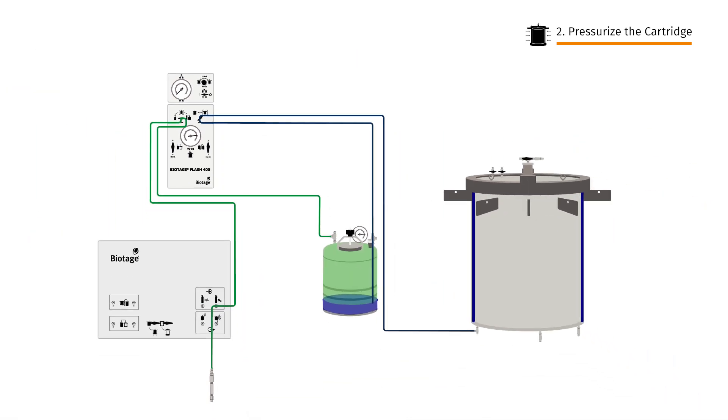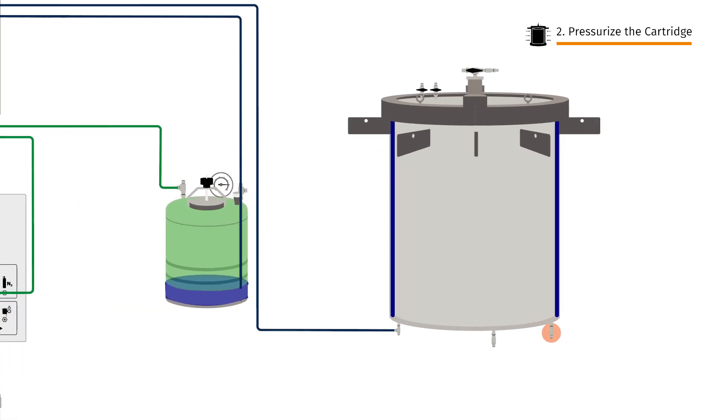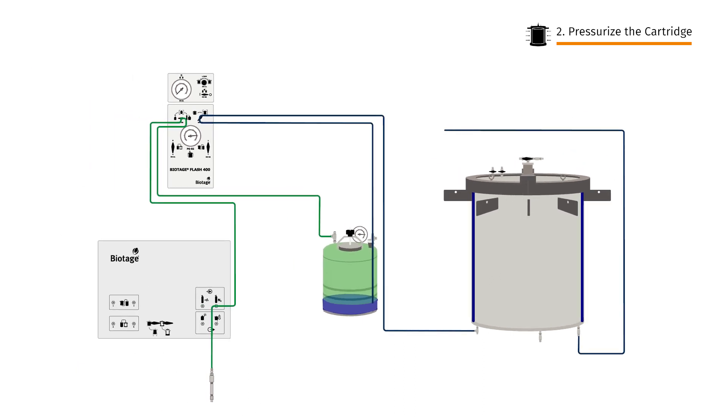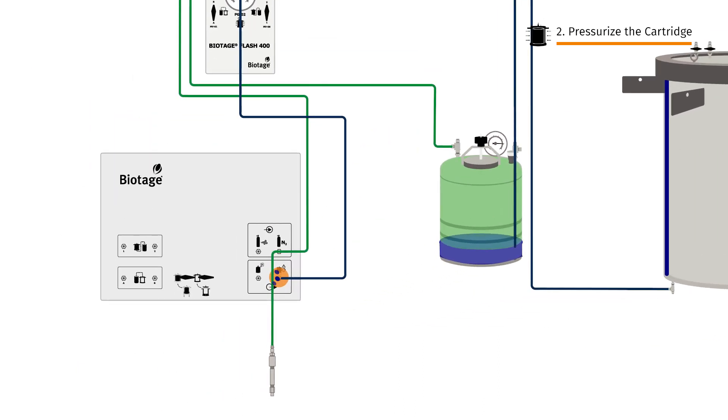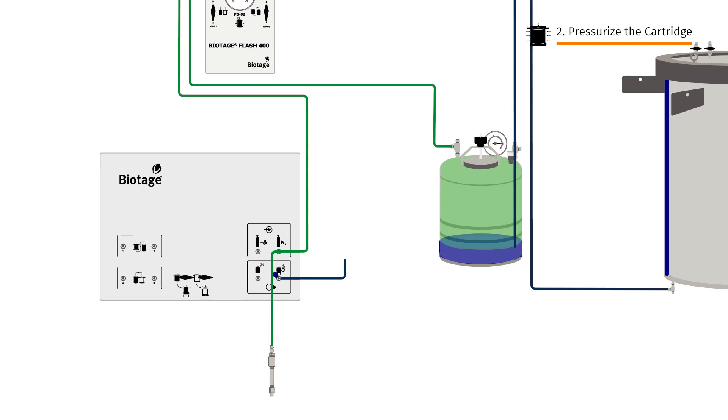Should the compression module be accidentally over pressurised at any time, a safety relief valve will open automatically to relieve pressure and allow fluid to pass safely via a relief port on the side panel.